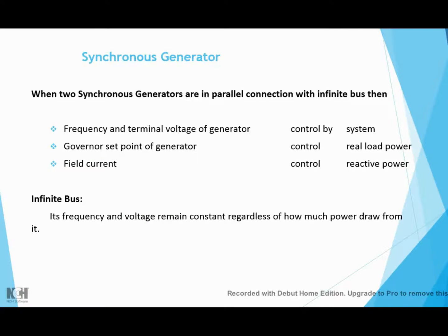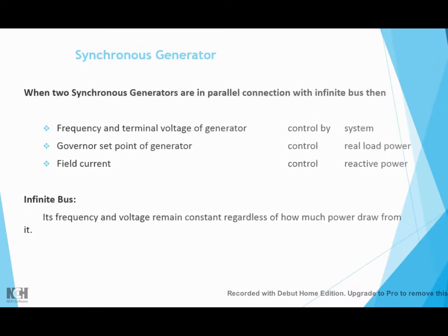When synchronous generators are in parallel connection with an infinite bus: frequency and terminal voltage of the generator are controlled by the system. The governor set point controls real load power, and field current controls reactive power.